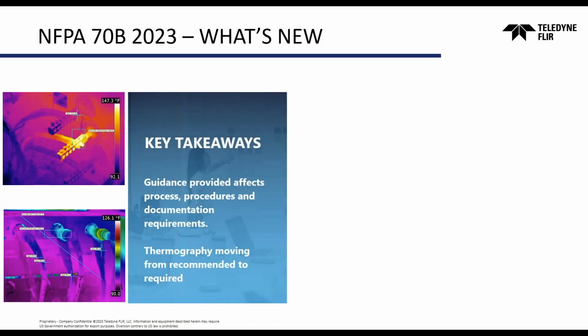So what is new? The key takeaway is that this guidance affects all process, procedures, as well as documentation requirements, and we're going to go into those specifically. The biggest change is that thermography has now moved from a recommended activity to a required activity. So all the references to thermography within the NFPA-70B guidance focus on that specific task, which has become a requirement now for compliance with 70B.